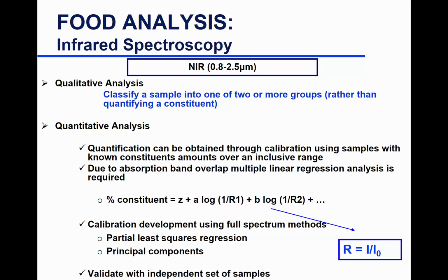Calibration is key. We have to calibrate using samples of different percentage of constituents to make sure we have calibration curves and the equipment is giving us as much of an accurate result as possible. And then we do validation by getting a set of samples and run it through that. We know the concentration within these samples, but we run it through anyway to test the calibration.